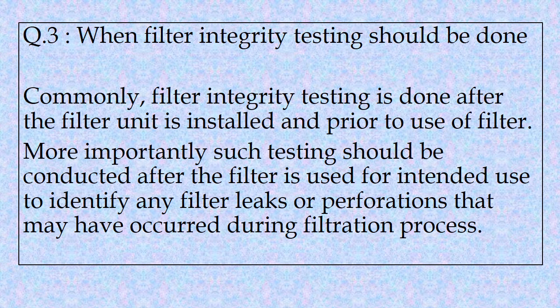Question 3: When should filter integrity testing be done? Commonly, filter integrity testing is done after the filter unit is installed and prior to use. More importantly, such testing should be conducted after the filter unit is used for its intended use, to identify any filter leaks or perforations that may have occurred during the filtration process.